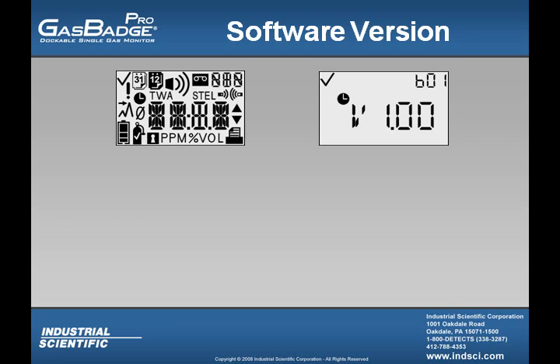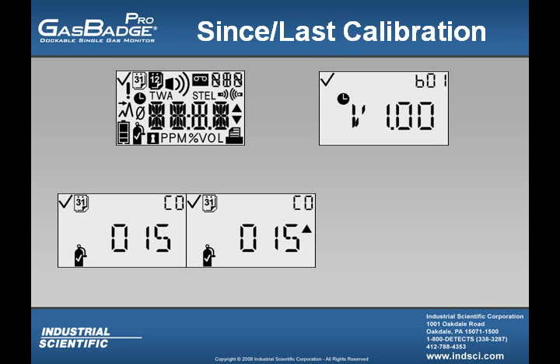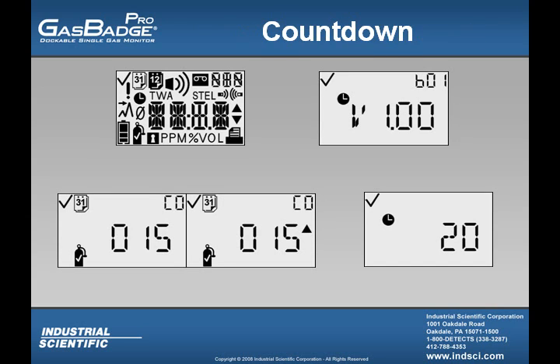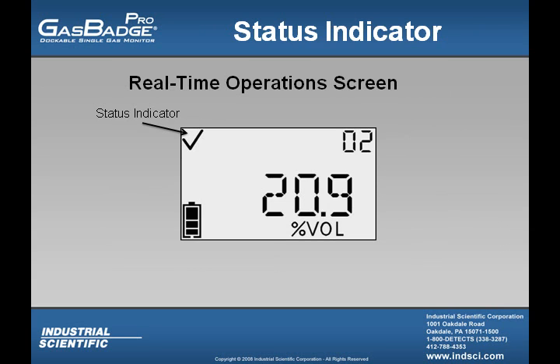From the startup screen, the user will see the software revision number of that particular instrument. They will see how many days since the last calibration, or how many days until a calibration is due, depending on how the GasBadge Pro is set up. Then the user will see the countdown screen. Once the countdown screen is done, the user is now in the real-time operation screen.